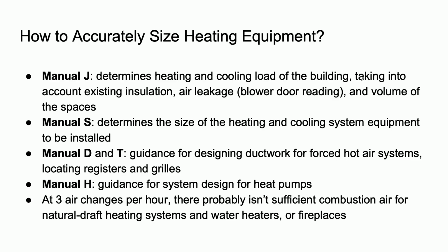If you want the rebate for the heat pump, it requires that you do a Manual J. So all heat pump contractors in Massachusetts know how to do it. They have to, to get the rebate. But we are not required to do that here in Maine. We have a much simpler heat pump sizing rule of thumb that we use here, and it is not as accurate. So that's why I will stand up on my soapbox.